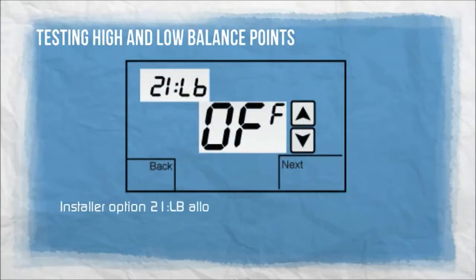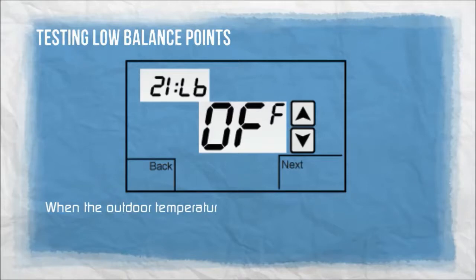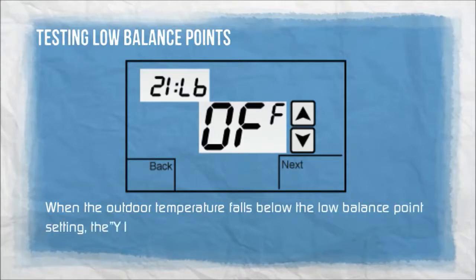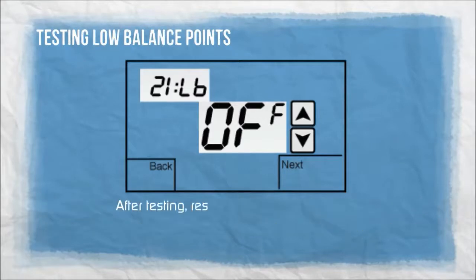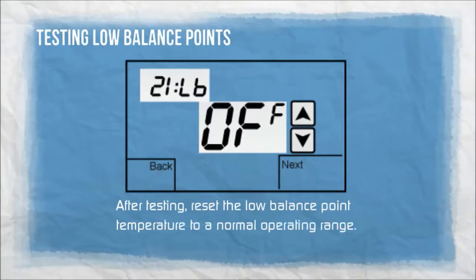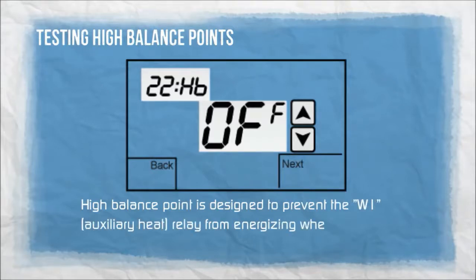Installer option 21LB allows you to select a low balance point temperature. When the outdoor temperature falls below the low balance point setting, the Y1 and/or Y2 compressor relays will be bypassed. After testing, reset the low balance point temperature to a normal operating range. High balance point is designed to prevent the W1 auxiliary heat relay from energizing when the outdoor temperature is above the balance point setting.